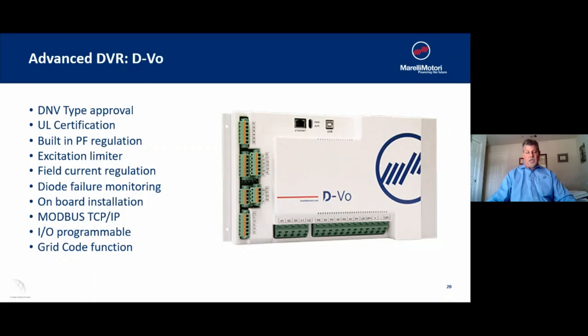Marelli's standard offering on our digital platform is the DVO and DVO Light. The DVO is society approved, so we can use it across the board including when paralleling with utility or for marine society approval on offshore projects. It's UL certified, has a built-in power factor regulator, is capable of excitation limitation and field current regulation, has diode failure monitoring, onboard installation has Modbus capability, has input/output programmable functions, and has a grid code function when paralleling with utility.